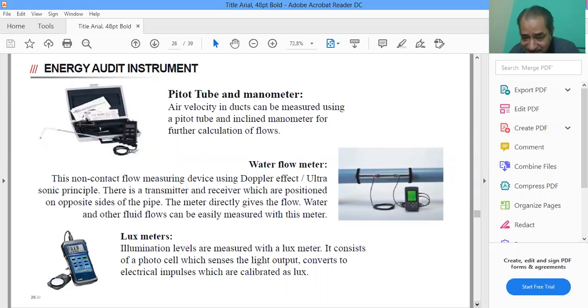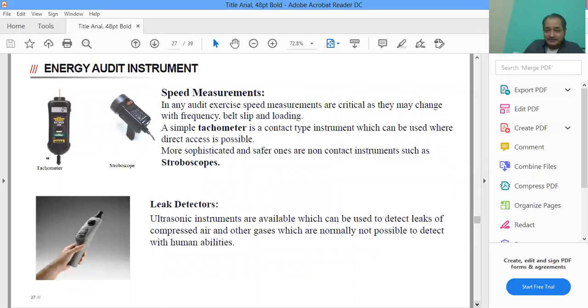Can I do with less? These are the meters you can see, and in slide 27 you'll see the speed measurements to be taken. For example, if my condenser fan in the air conditioner is running at a certain RPM, do I need to increase it? Through a stroboscope, a non-contact type meter, you can measure the RPM of a particular equipment while it's performing.